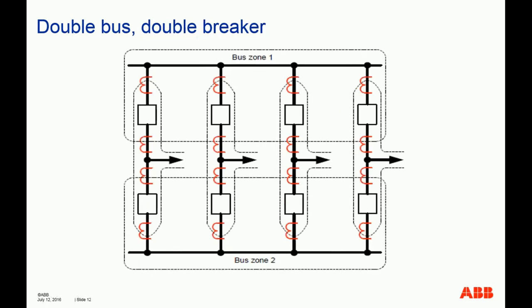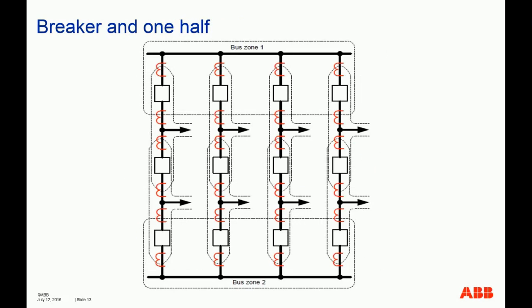Double bus, double breakers. This is probably one of the most expensive types of bus configuration, because each of your lines, transformers, or loads is actually protected by two breakers. So of course you can take any of the two breakers out of service at any time and allow the other bus to feed the load. So it's very, very flexible and versatile and reliable, of course.